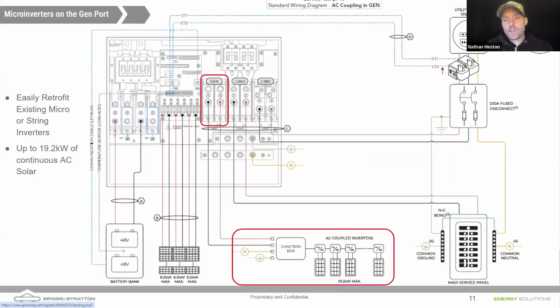Now, I'm going to point out in the next few slides, these are wiring diagrams right out of a Sol-Ark manual. These are out of the Sol-Ark 15K manual. Different uses of the gen port. What I'm showing right here is an example where you've got a retrofit. You might have an old inverter on the house. You've already got your permit for that inverter. You don't want to get up on the roof and change things.